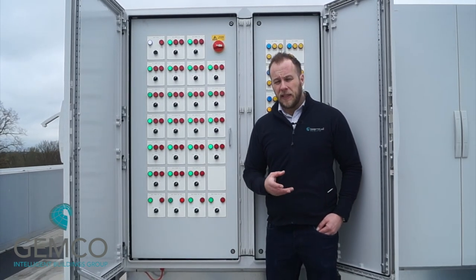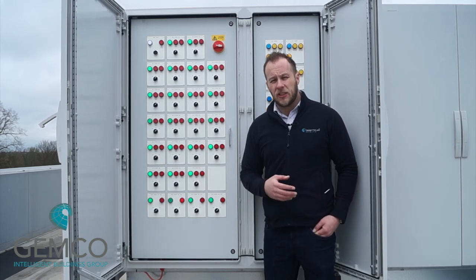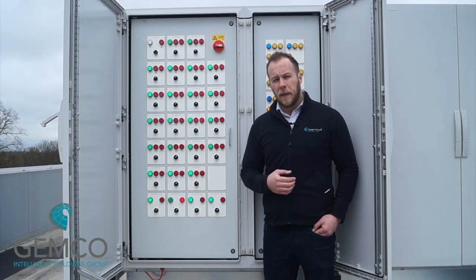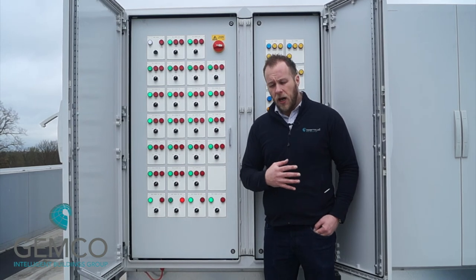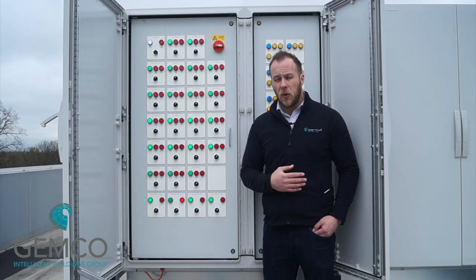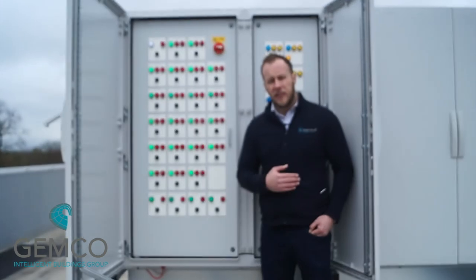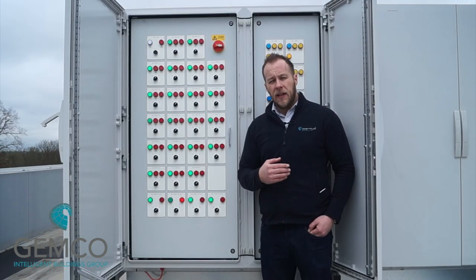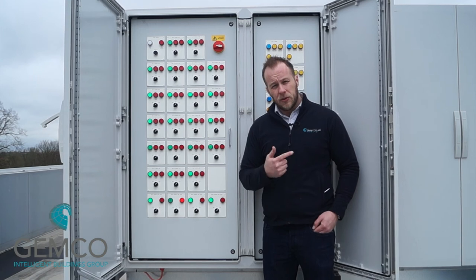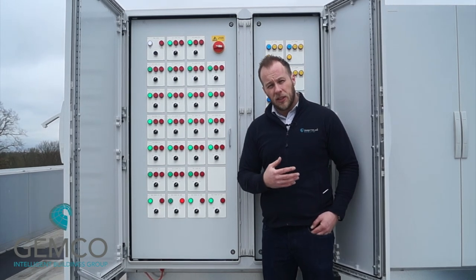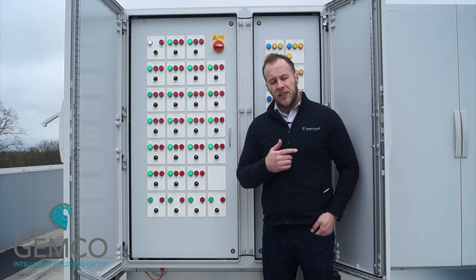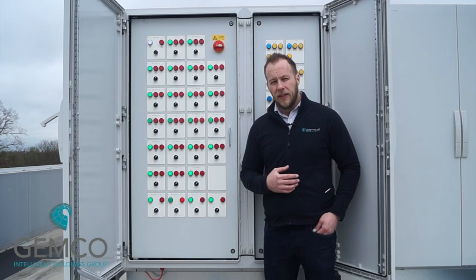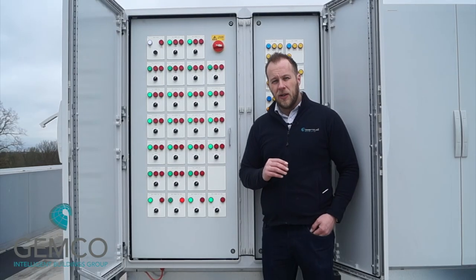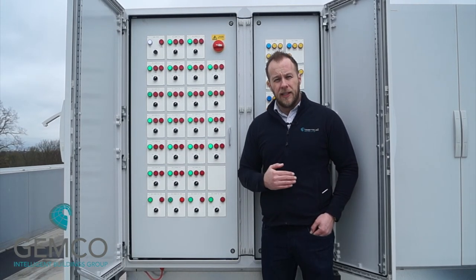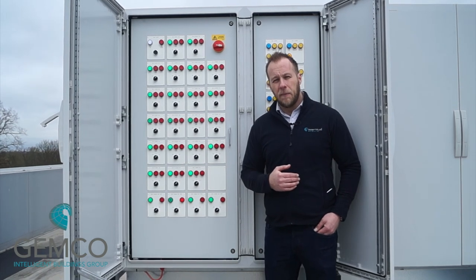The set point's been defaulted to 21 degrees. That's adjustable via the head end or the BMS display panel. If it can't cope with 21 degrees, so if it's a cold day and it can't quite get to 21 using just the thermal wheel, then it will initiate the three-port valve to use some of the hot water from the constant temperature circuit fed from the boilers, just to top that up to get to 21. There's a three-port valve on each unit, and that just modulates to allow less or more water in depending on how much it needs to get to set point.